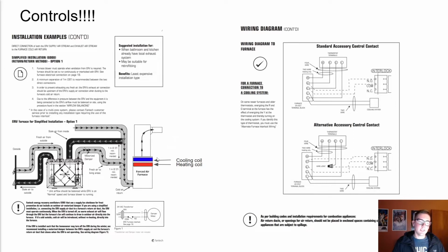And second thing that could happen is if your ERV is off and your furnace is on, and you don't install this motorized damper that Fantech does call out as their solution to this, if you don't have that motorized damper there and your furnace comes on and your ERV's not on, your furnace could be pulling unconditioned 32 Fahrenheit air in, and really your heating element would struggle to keep up with that, and it could cause damage. And also, just like the other described scenario, you could have discharge air that's not conditioned fully like you want it. So that's the beauty of this setup.